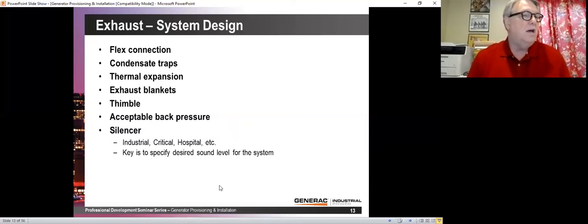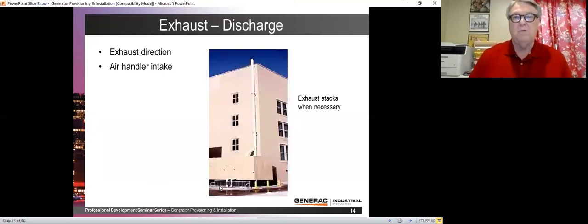You need to look at the total sound from the generator. Here's the exhaust. You can see that above the generator, there are some windows that can be opened. And so we've taken the exhaust pipe up quite high. As you would guess, if you bring the exhaust pipe up that far, then you're going to have to make that exhaust pipe larger in order to prevent excessive back pressure on the engine. Excessive back pressure on the engine is going to limit the amount of power that engine can produce.